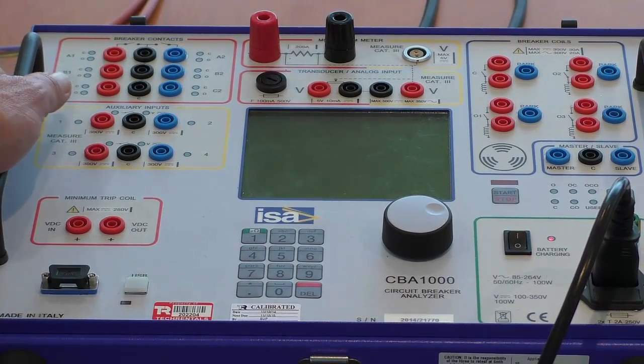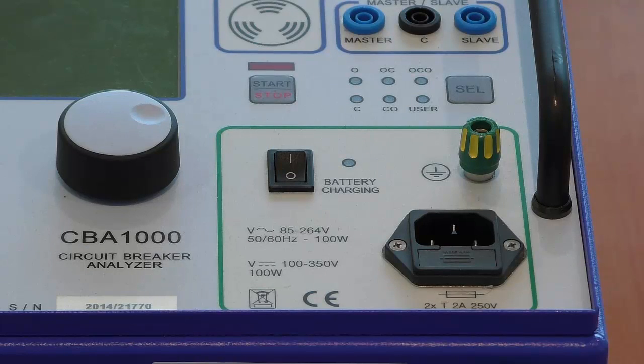Today we have the CBA 1000 circuit breaker analyzer from ISA, which provides basic timing testing for the circuit breaker main contacts and auxiliary contacts. In order to make the set operational, the following basic wiring is required. An earth should be applied to the substation earth at a convenient point.